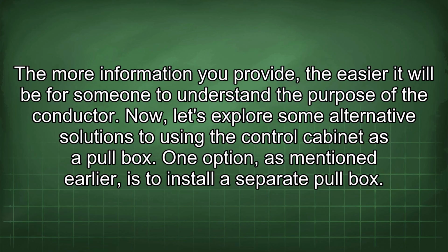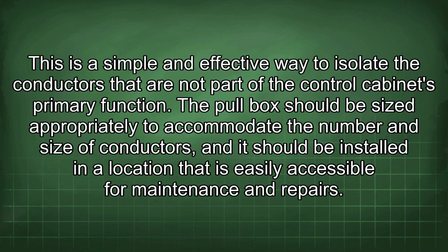Now let's explore some alternative solutions to using the control cabinet as a pull box. One option, as mentioned earlier, is to install a separate pull box. This is a simple and effective way to isolate the conductors that are not part of the control cabinet's primary function. The pull box should be sized appropriately to accommodate the number and size of conductors, and it should be installed in a location that is easily accessible for maintenance and repairs.